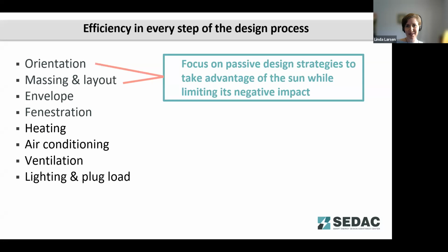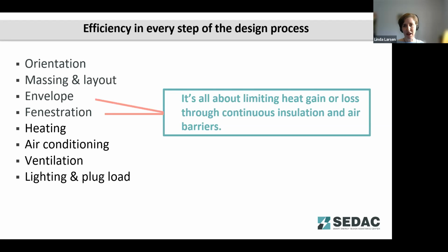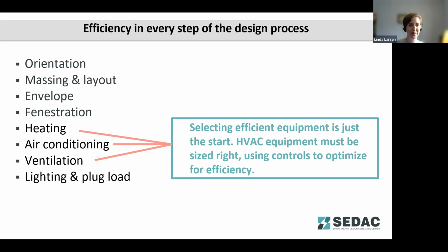All right. So just a very quick high-level overview, review of what we've talked about, emphasizing again that efficiency should be considered in every step of the design process and construction process as well. So orientation, massing, and layout, the focus there is on passive design strategies that take advantage of the sun while limiting its negative impact. And then with envelope and fenestration, it's all about limiting the heat gain or loss through continuous insulation and air barriers, and paying close attention to those points where you might have thermal bridging.